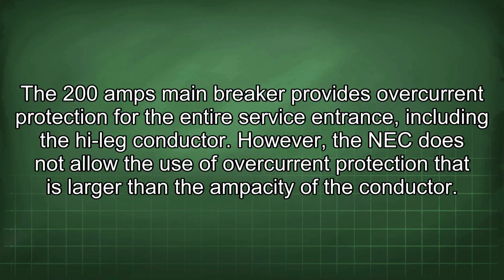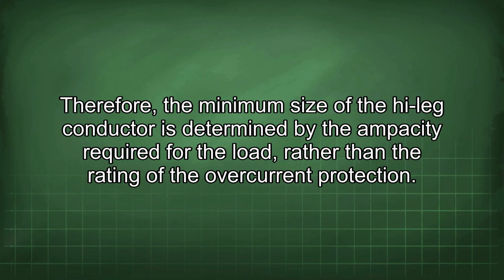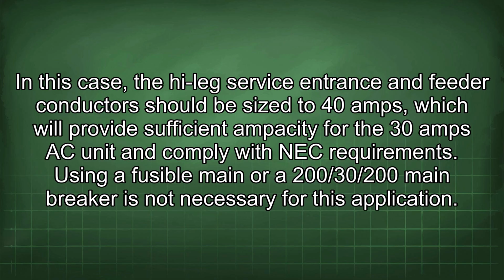However, the NEC does not allow the use of overcurrent protection that is larger than the ampacity of the conductor. Therefore, the minimum size of the high leg conductor is determined by the ampacity required for the load, rather than the rating of the overcurrent protection. In this case, the high leg service entrance and feeder conductors should be sized to 40 amps, which will provide sufficient ampacity for the 30 amps AC unit and comply with NEC requirements. Using a fusible main or a 200/30/200 main breaker is not necessary for this application.